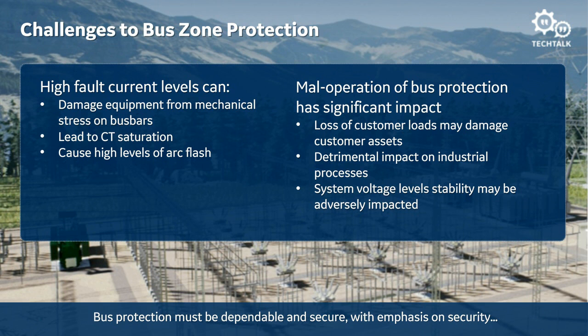Conversely, mal-operation of the bus protection system has significant impact, including customer outages, process downtime leading to financial impact, and voltage stability issues that can adversely affect other equipment. A more serious case is widespread system collapse, such as the 2003 Northeast Blackout — I was living in New York City at the time; it was not pleasant in the middle of August. Therefore, we must design a dependable and secure bus protection scheme. Increasing dependability may sacrifice security, and for the most part we emphasize security to keep customers online.